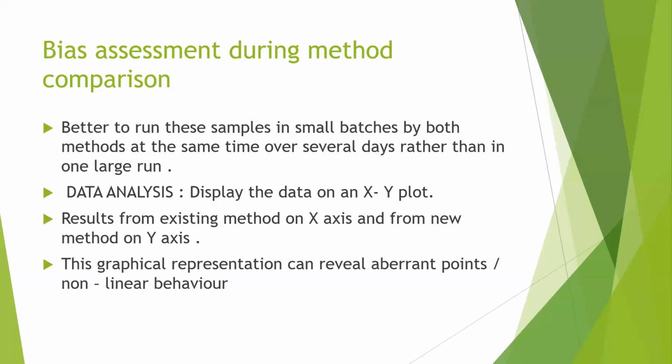In fact, when you tell your labs how to do a method verification exercise, it is a duty of the quality team, or whatever is the corresponding team in your organization, to specify that we must run these samples over a minimum of 10 days, and also that we must have all the samples of our interest: normal, abnormal, low, normal, high, and so on. Now, how do you analyze the data?